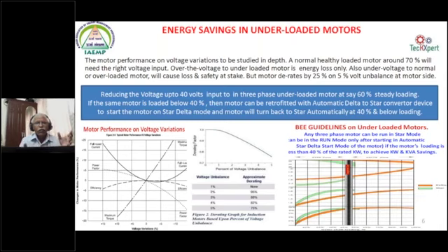It will definitely bring down the energy savings by 10 to 20%. Each one depends on the application that is used. For all the material handling applications, when there is a high torque load to start with and then a low torque, it will definitely have savings depending on the loading. And if the loading is steady, this can be used. And this is a low cost retrofit.